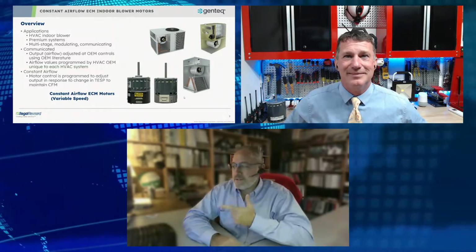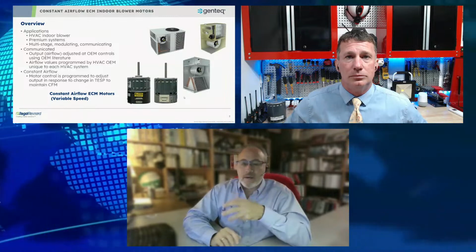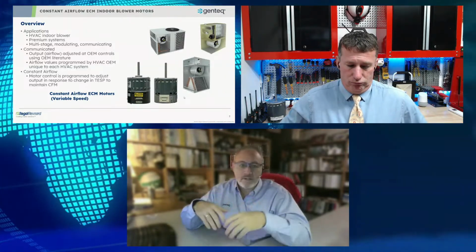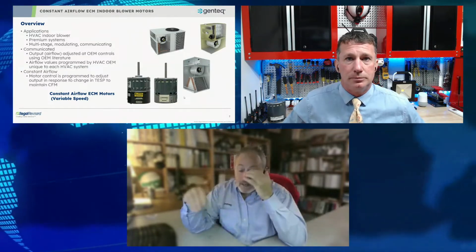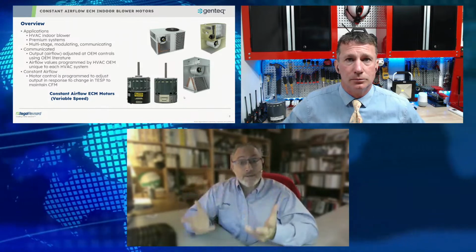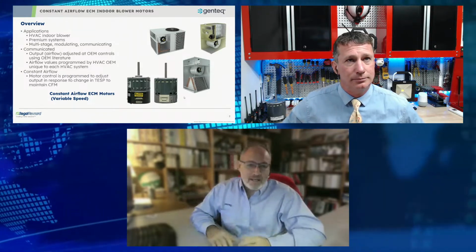Yeah, and the main reason I like to bring that bullet point up is, I get asked quite often, can I take an ECM from a carrier, and it looks the same, has the same plugs, and put it in a Trane? Right. And I've even had people tell me, well, I've done that and it works. So what do you think about that? Because they'll hear me say, no, you can't do that.